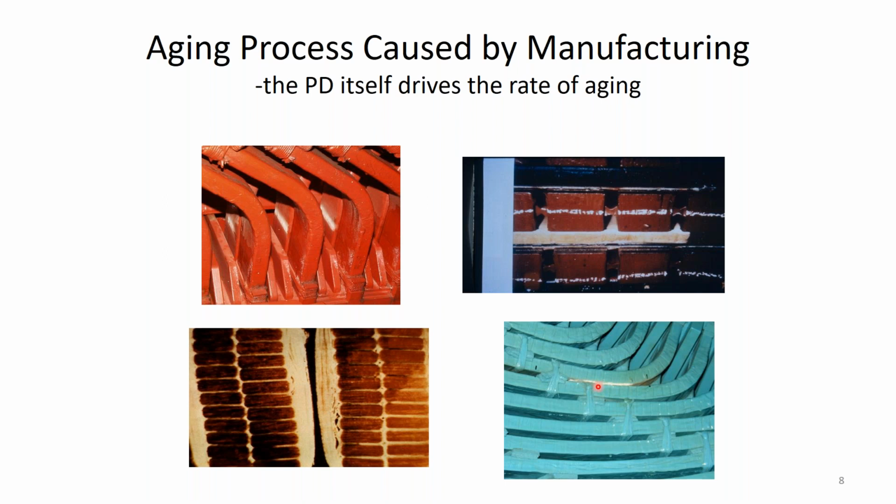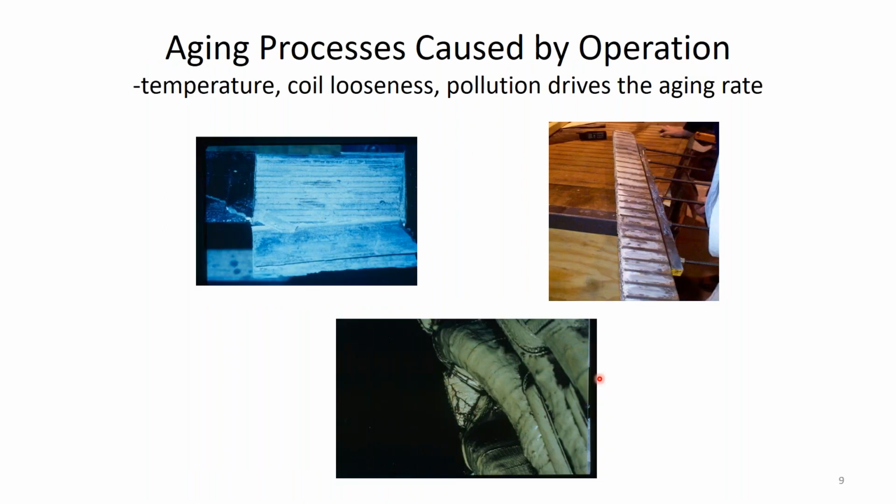It should have been much wider. We got PD, and the PD gave rise to nitric acid and created that white powder. But these are all very slow failure processes, usually taking many years, if not decades, to cause failure. Okay, and hopefully you won't be having those on your particular machines.